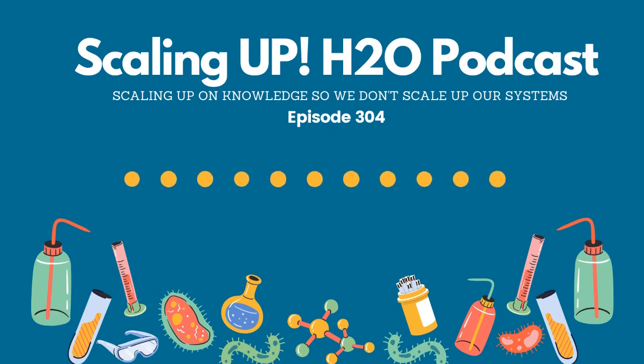That's been a big issue of late, and what a lot of the manufacturers have started doing, because we would get corrosion coupons that we just bought straight from the factory and it would have signs of corrosion on them. They're actually now starting to wrap the corrosion coupons in special VCI paper and then putting those into the envelopes that are impregnated with the volatile corrosion inhibitor, the VCI compound.